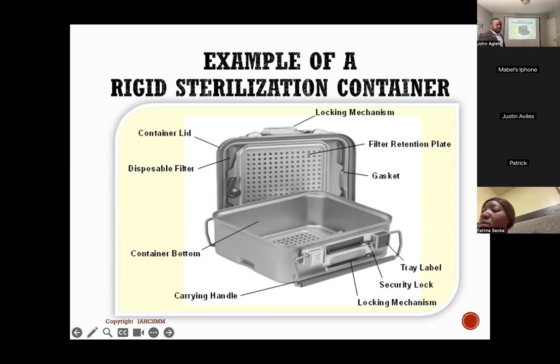Another filter. If the container is just all together, if there are no filters at the bottom, during the steam sterilization process where drying is required, it will be very, very challenging, or very difficult, for the contents to dry properly, okay? So for the most part, most of these rigid containers will have filters or holes at the bottom and some on the top. It is not the end of the world if you get a container that has a filter on the lid and not at the bottom. Some of the containers do not have filters at the bottom. Don't say you cannot use it because John said the containers should all have filters.